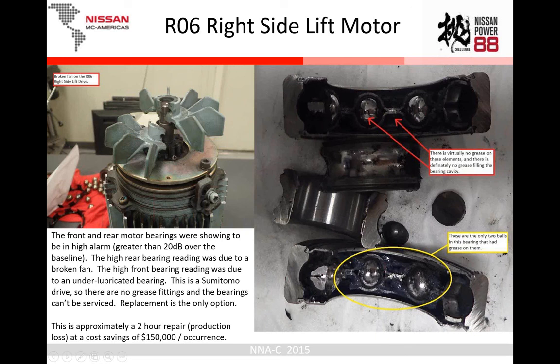We cut this bearing apart, and there's absolutely no grease on half of it. There are only a couple of elements in this bearing that have grease on them - not packed, but a little bit. So it's interesting to see whenever an ultrasound alarm goes high, you want to know why, even though sometimes you can't find out because you have to send it out for repair - it's a high-end motor or something. But in this case, we took this one apart, cut it open, and found out what the problem was.